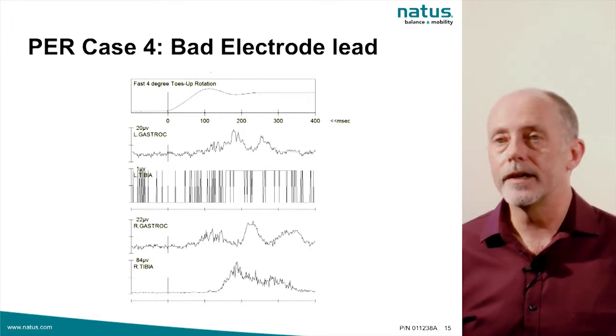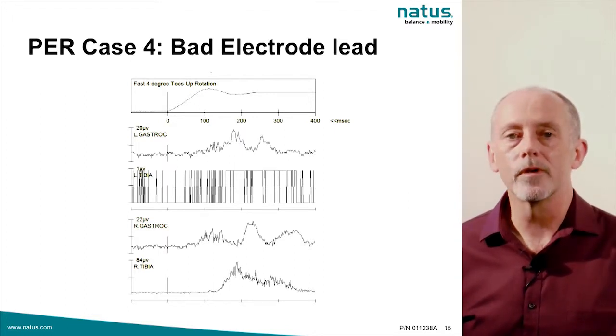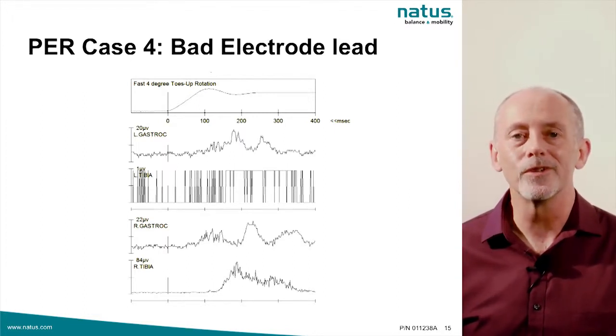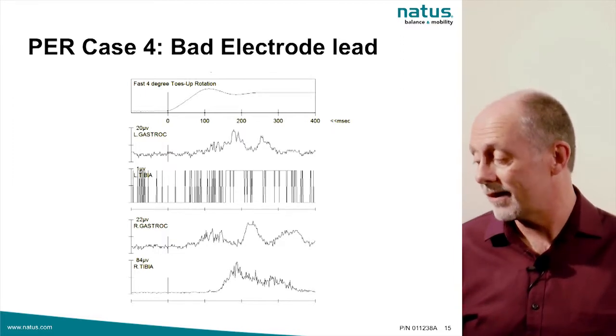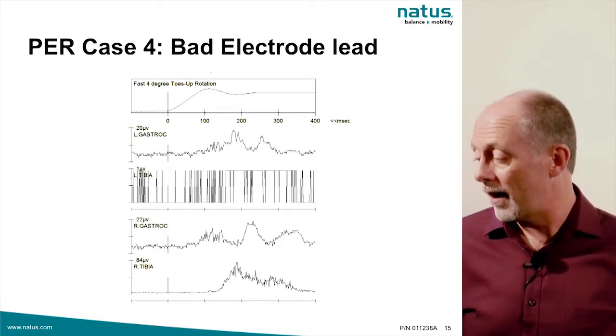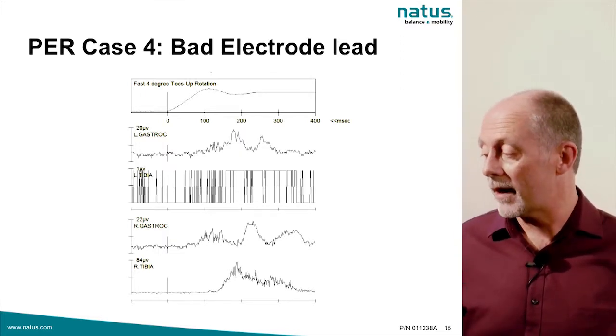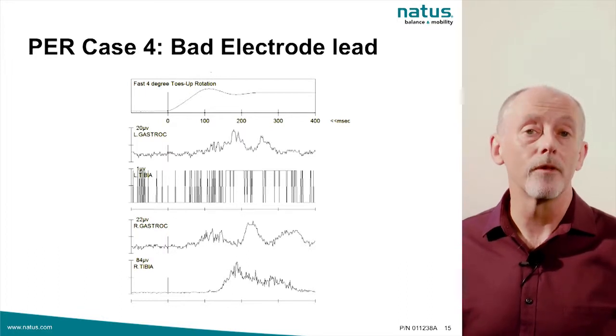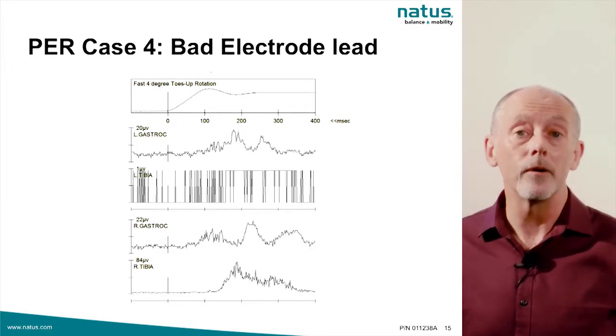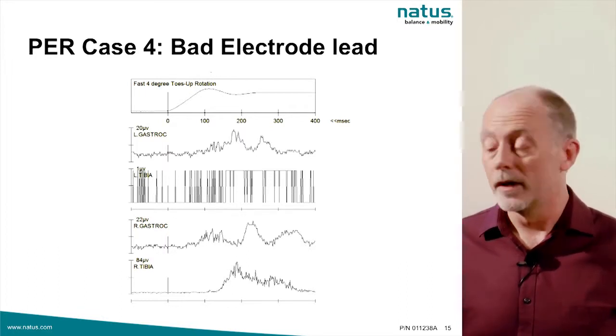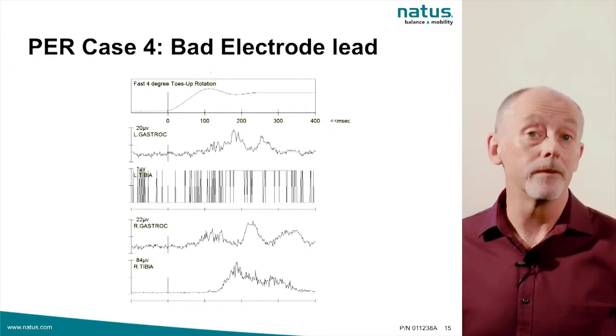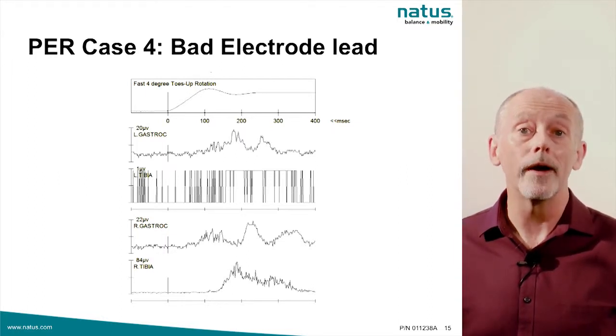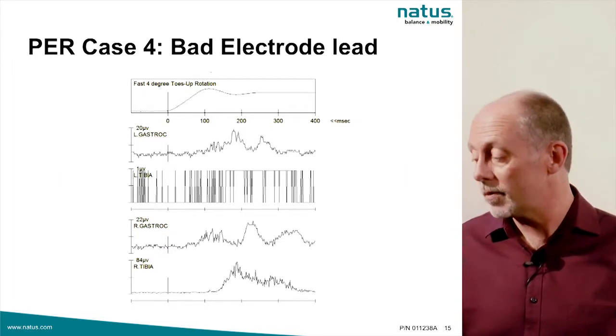This is a real-world test, and in the real world electrodes and wires go bad — and that's what it looks like when you've got a bad electrode lead. Typically the way to repair that is to first try replacing your disposable electrode. If that doesn't resolve it, you may have a bad electrode wire that needs to be replaced.